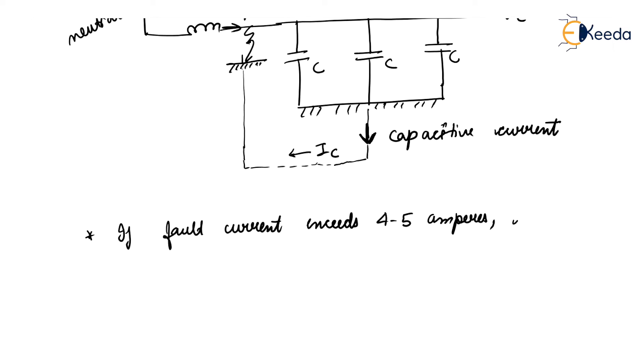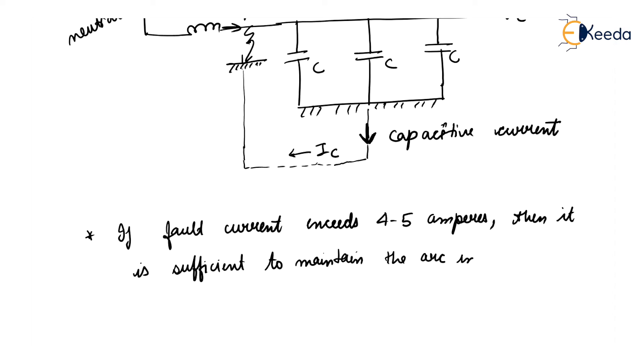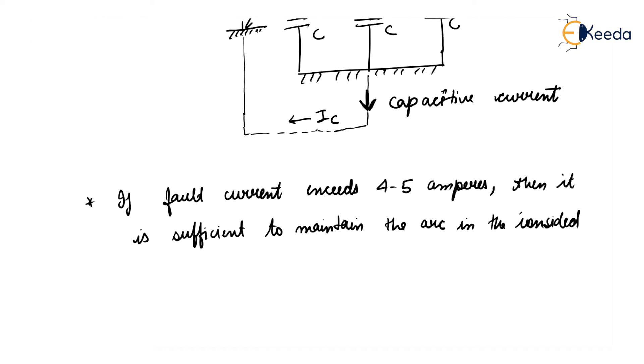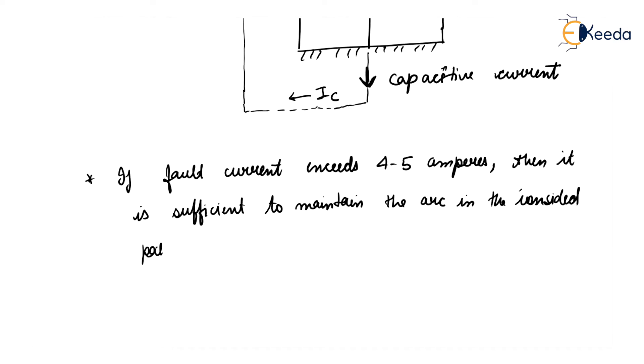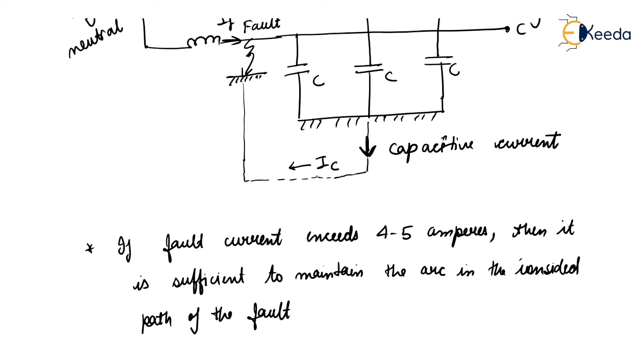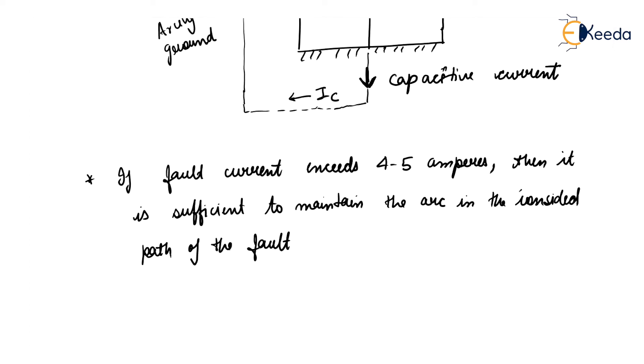The capacitive current over 4 to 5 amperes flowing through the fault gives rise to an arc in the ionized path of the fault. This is arcing ground, even though the fault has cleared itself.